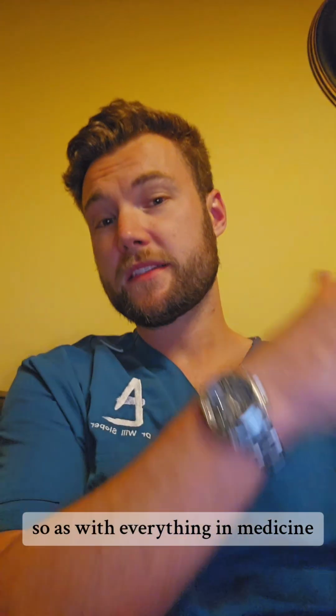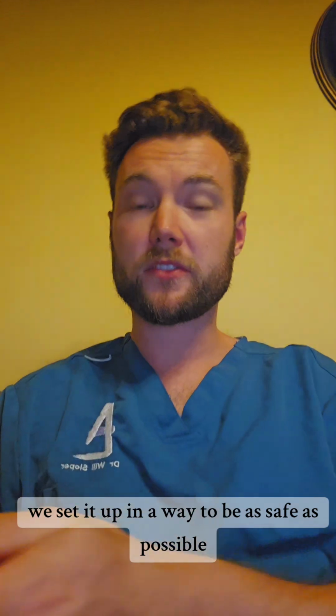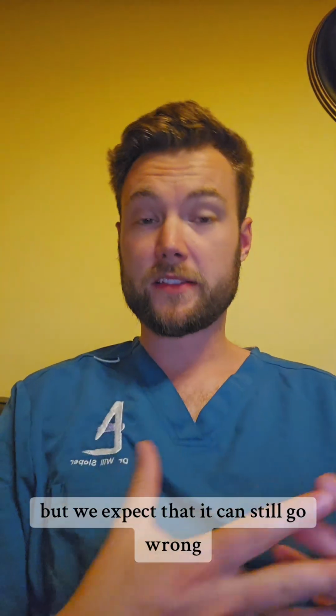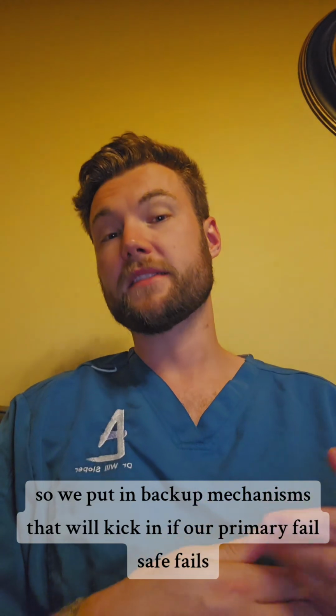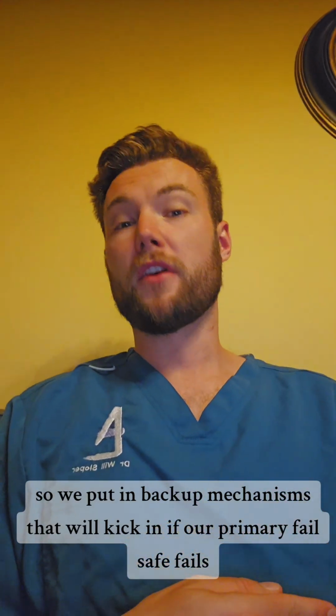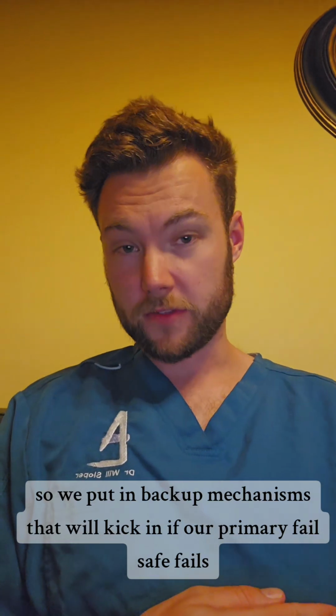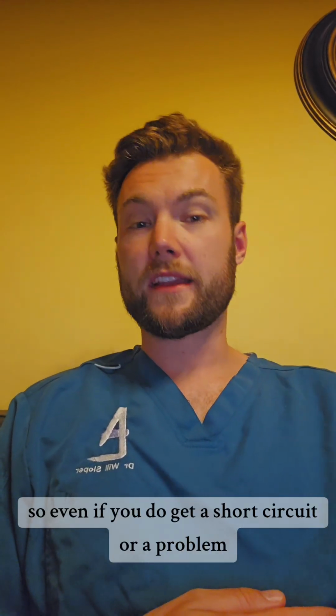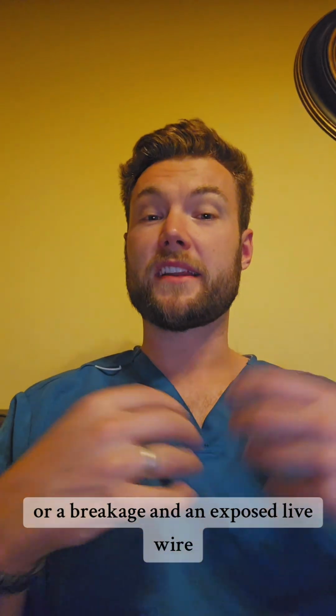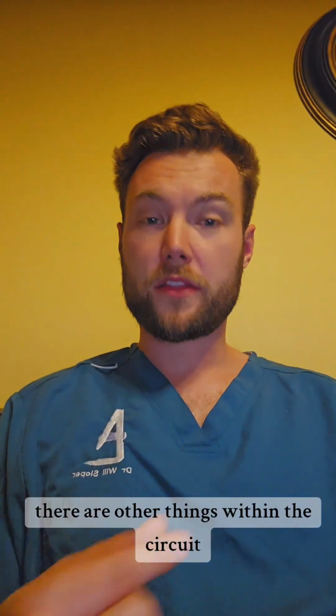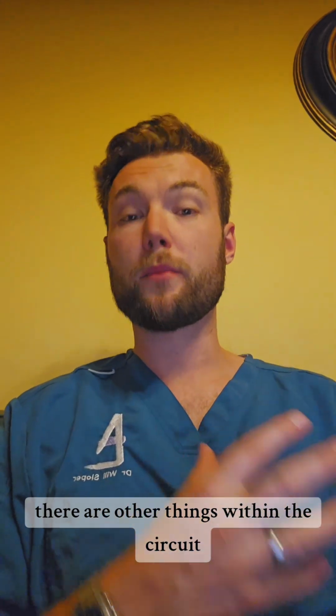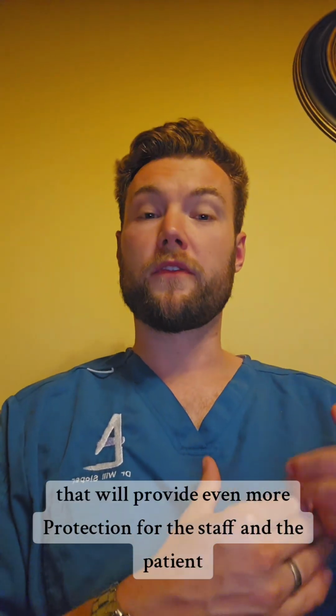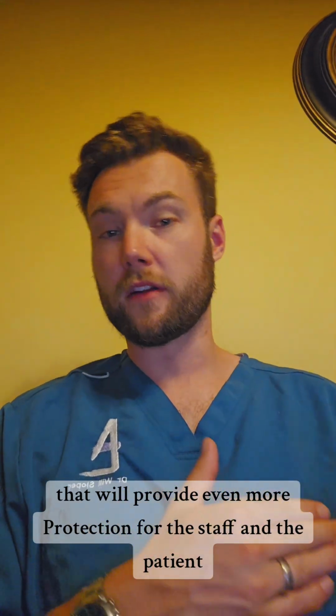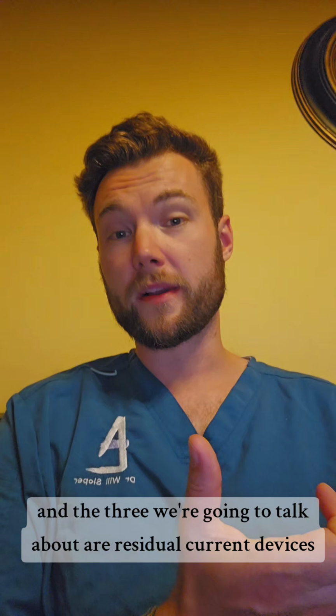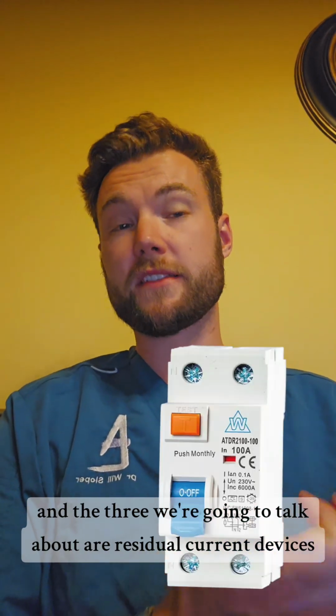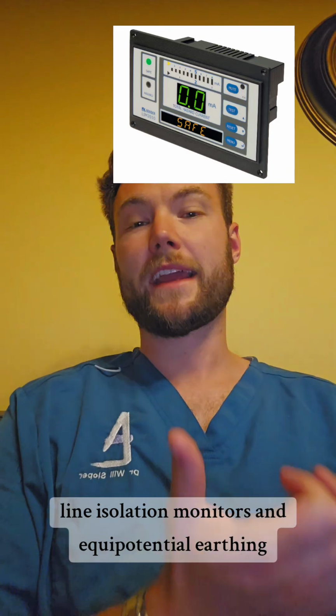So as with everything in medicine, we set it up in a way to be as safe as possible, but we expect that it can still go wrong. So we put in backup mechanisms that will kick in if our primary fail-safe fails. So even if you do get a short circuit or a problem or a breakage and an exposed live wire, there are other things within the circuit built into the machinery that will provide even more protection for the staff and the patient. And the 3 we're going to talk about are residual current devices, line isolation monitors, and equipotential earthing.